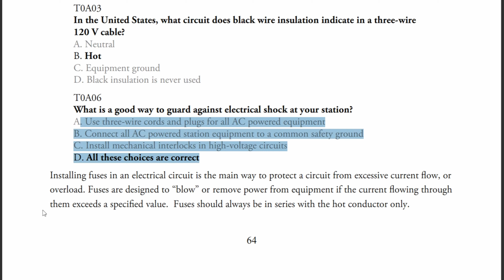Installing fuses in electrical circuits is the main way to protect a circuit from excessive current flow or overload. Fuses are designed to blow or remove power from the equipment if current flowing through them exceeds a specified value. Fuses should always be in series with the hot conductor only - it's not recommended to put a fuse on the negative side. I have seen people do it, and I have seen manufacturers do it as well. It's not really recommended, but it is done.